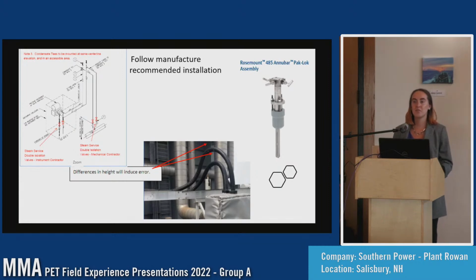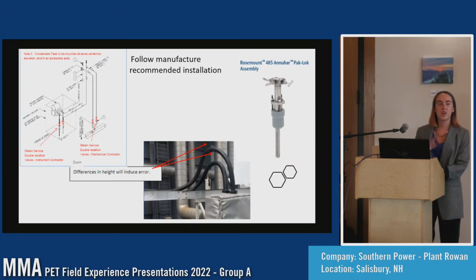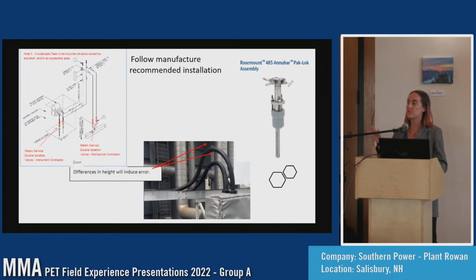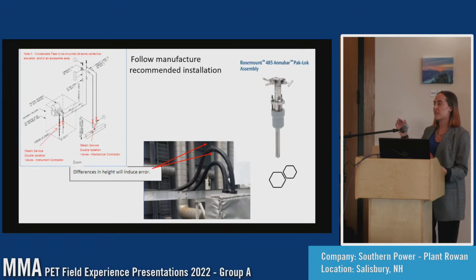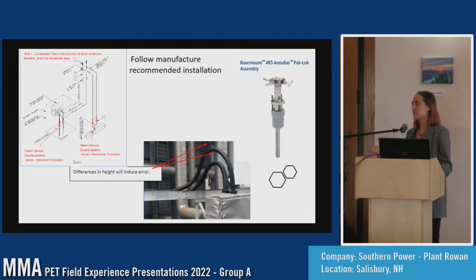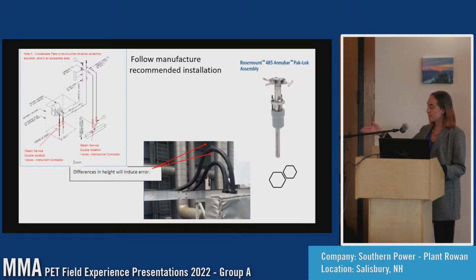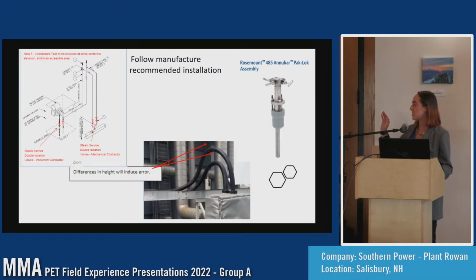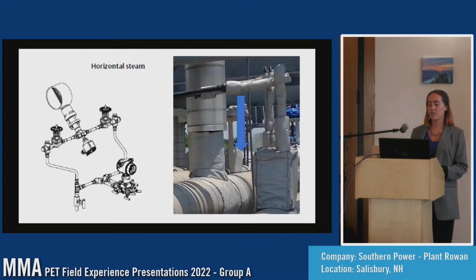What I would recommend is that they follow the manufacturer's recommendation, which was 45 degrees off the bottom, with the sensing lines either level or coming out below the instrument. The other two recommendations that SPS engineering came up with were to just move the sensing lines from above to level and or below the instrument, and or replace the annubars with flow tubes, which would be hugely expensive and take a lot of time. The manufacturer recommendation would only cost $11,500, and replacing the annubars with flow tubes and moving the sensing lines would cost $17,500, so just a lot more work and hugely expensive.